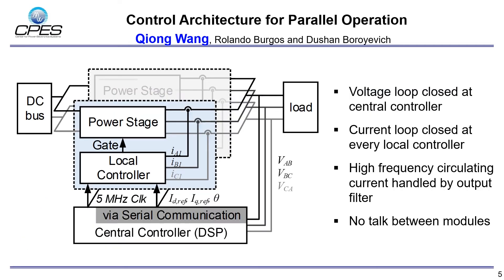Here shows the control structure for paralleling two modules. The control implementation consists of a central controller for the voltage loop and local controllers for current loops. There is no communication between the local controllers, and there is no active control on circulating current between the modules. As each module controls their own output current, there shouldn't be low-frequency circulating current if the current controllers are functional. The high-frequency circulating current is mitigated by the output common mode and differential mode filters.